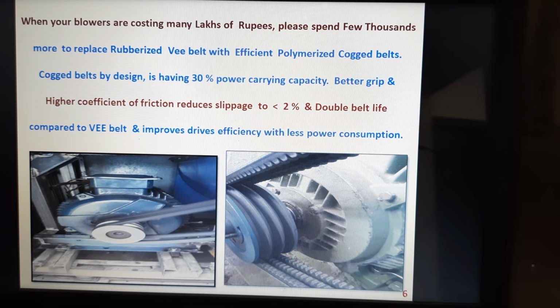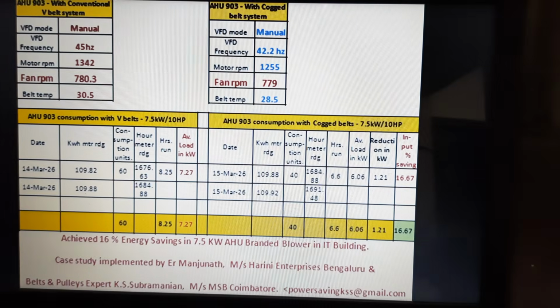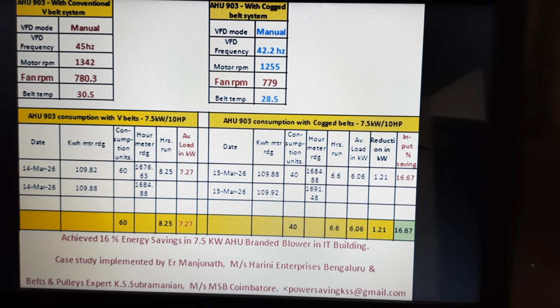You can see in the images how heavy and oversized the V-belts are on an AHU blower, and how clearly the cogged belt performs on a matched pulley. This case study was done on an IT building in Bangalore, on almost 7.5 kilowatts. During the study, the VFD was kept on manual and the frequency was kept at 45 Hertz, and the fan RPM was maintained at 780 RPM.